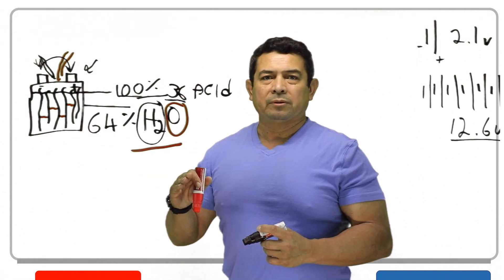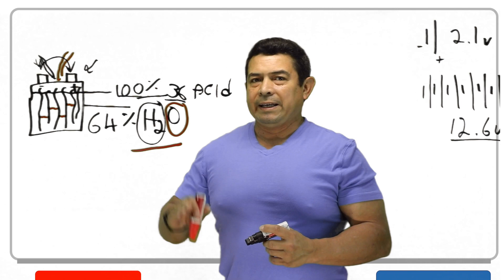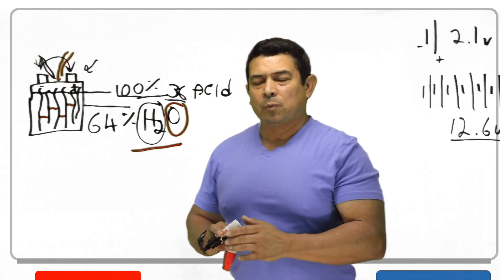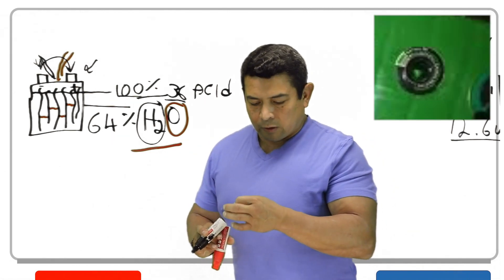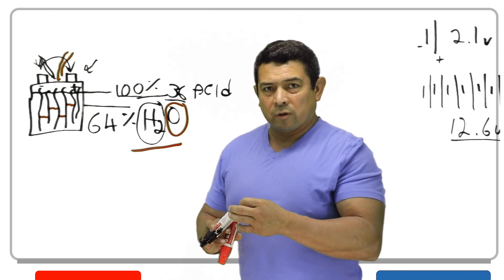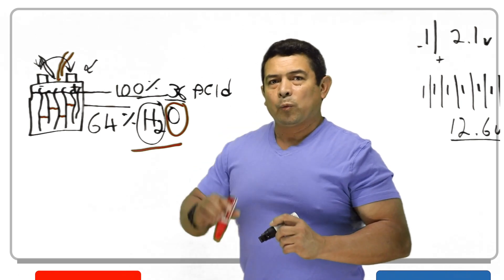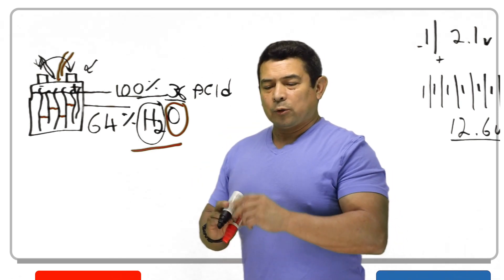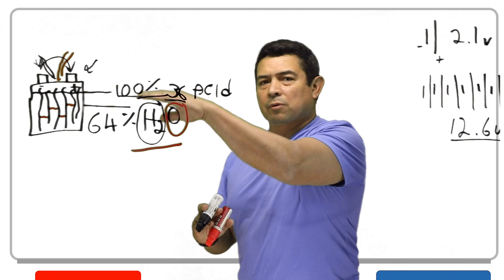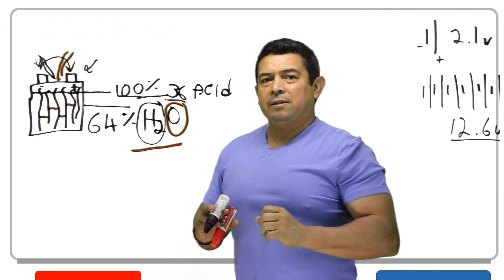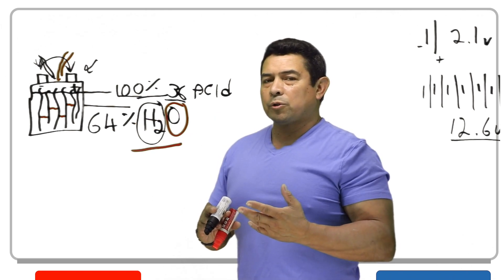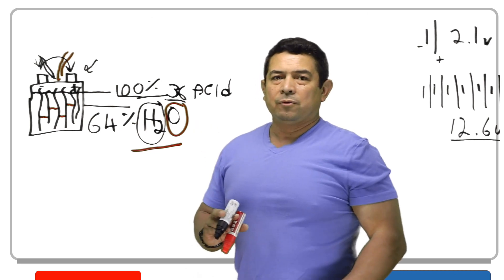If you have just a regular battery, then at some point the water level may drop and you're going to have to add H2O. Some of you have probably seen the ones that have a little sight glass on them that is supposed to be green. When it's not green anymore, the battery is no good. It has a little float inside — as the level drops, you can't see the green anymore. To cure that, you would add H2O.